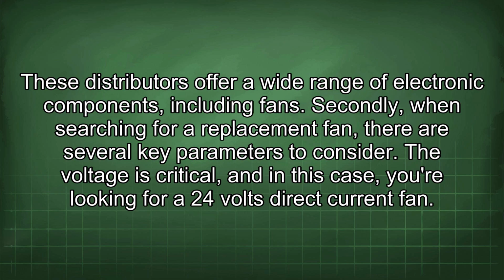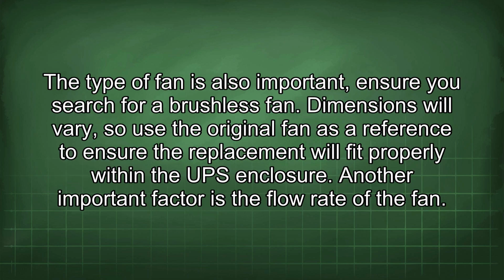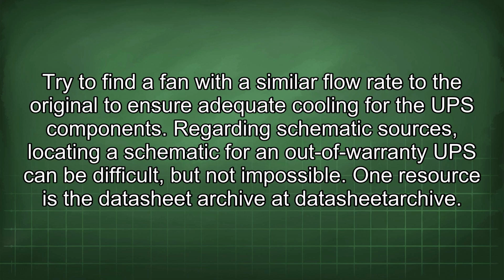Secondly, when searching for a replacement fan, there are several key parameters to consider. The voltage is critical, and in this case, you're looking for a 24 volts direct current fan. The type of fan is also important. Ensure you search for a brushless fan. Dimensions will vary, so use the original fan as a reference to ensure the replacement will fit properly within the UPS enclosure. Another important factor is the flow rate of the fan. Try to find a fan with a similar flow rate to the original to ensure adequate cooling for the UPS components.